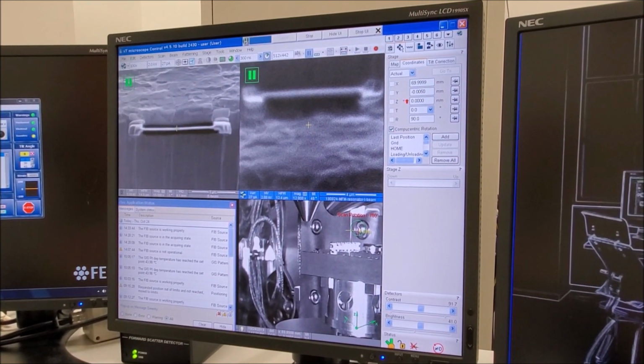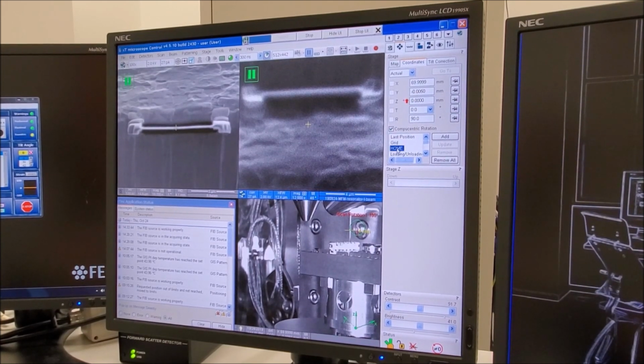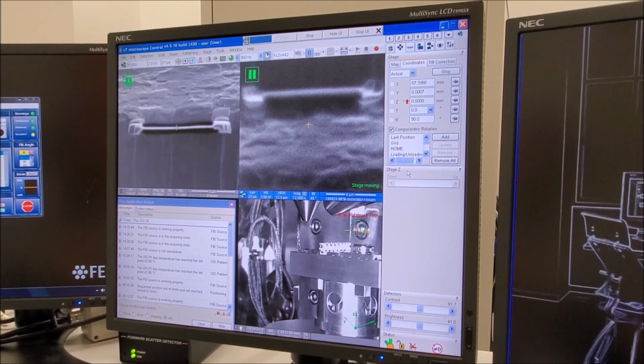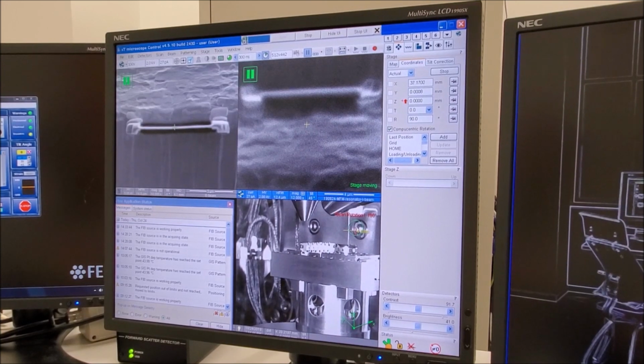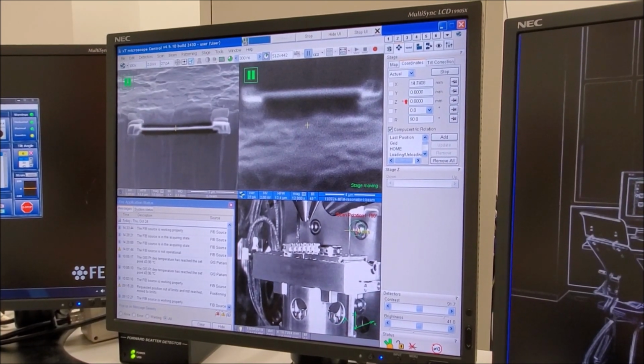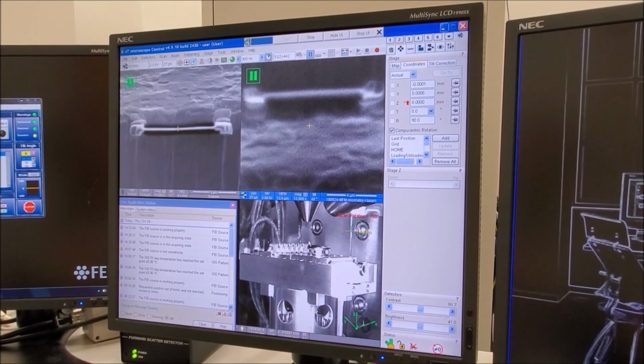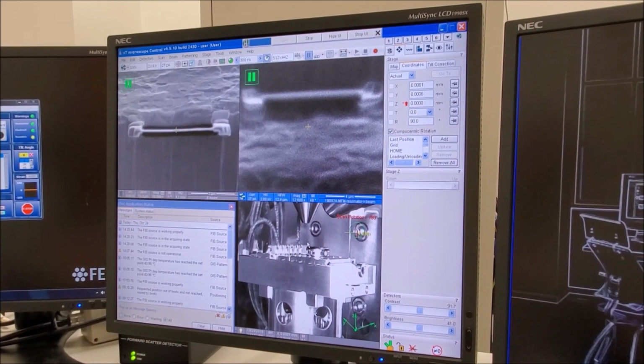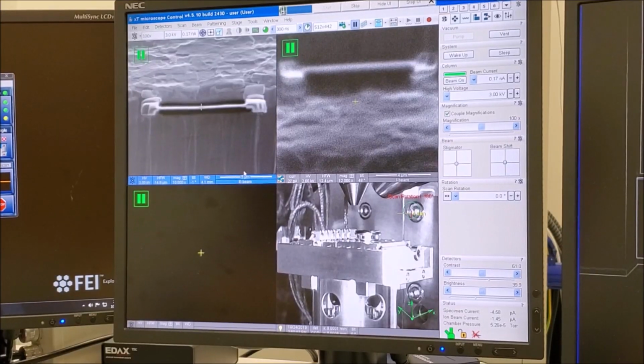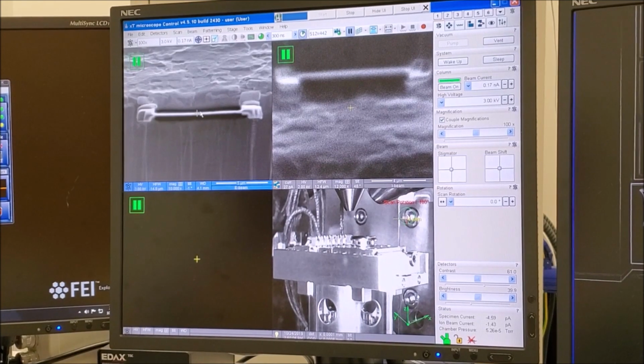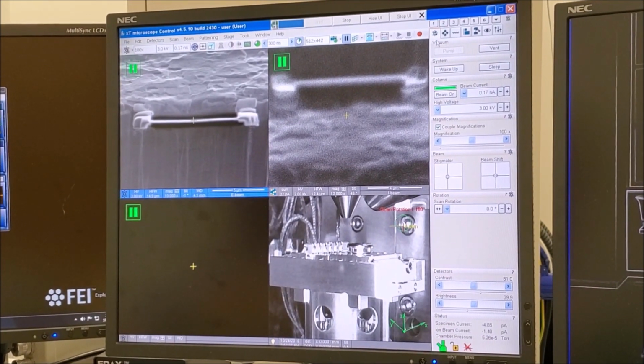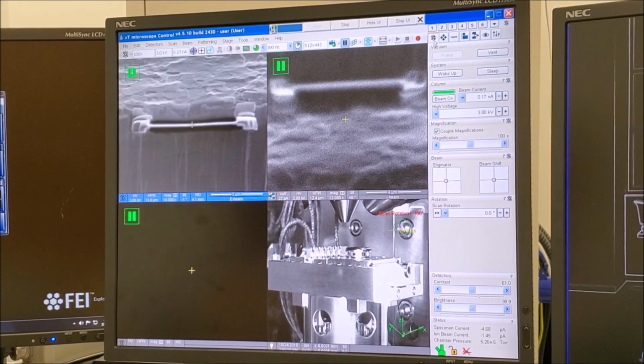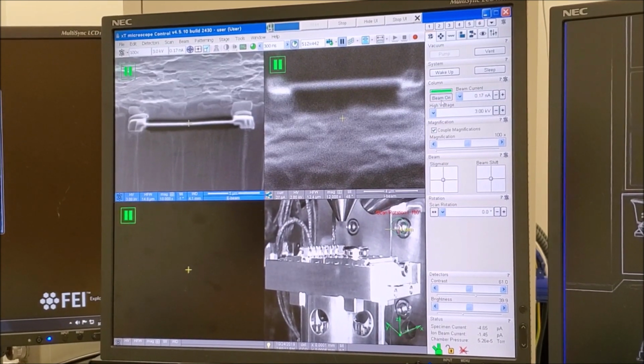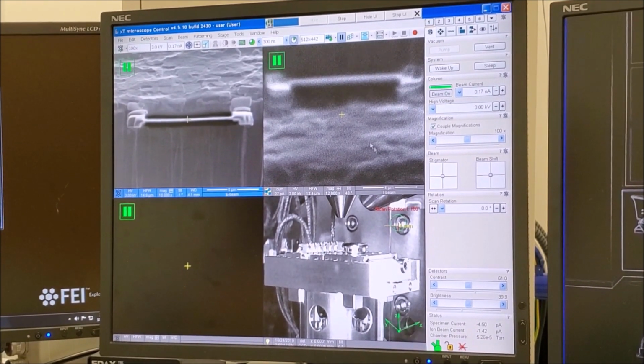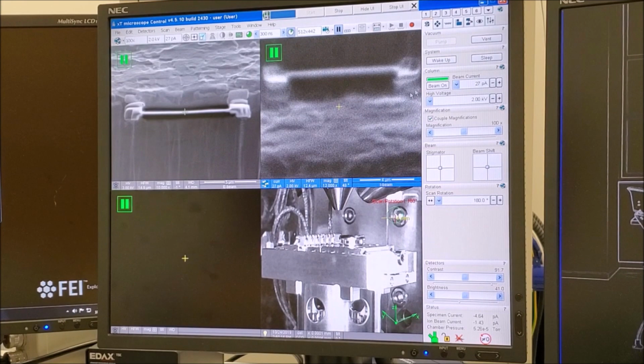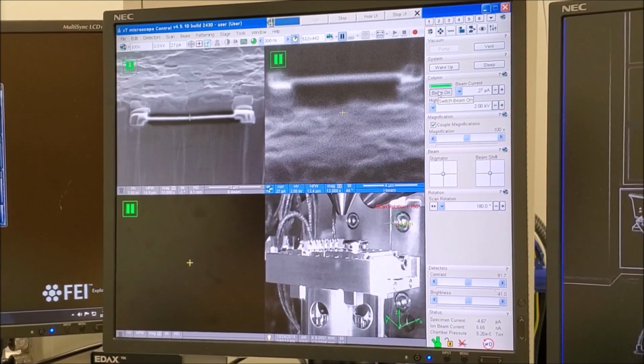Then enter the navigation module. Under the list of stored stage positions, select Home to drive the stage to the home position such that the modules are directly under the electron beam column. In the beam control module, beam on will be selectable once sufficient chamber vacuum has been achieved. With the E-beam quad activated, select beam on to turn on the beam. Activate the I-beam quad and do the same.